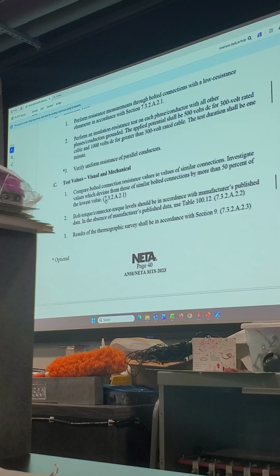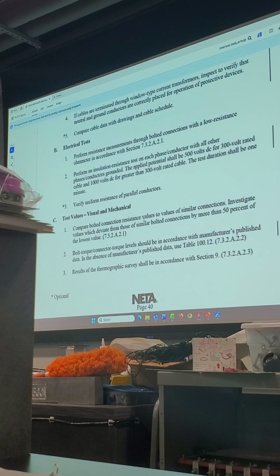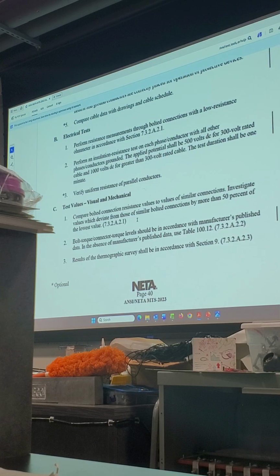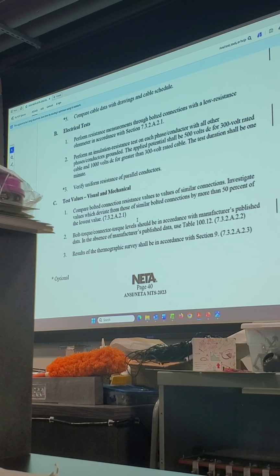So C, test values for visual mechanical: compare bolted connection resistance values to values for similar connections. Investigate values which deviate from those of similar bolted connections by more than 50% of the lowest value. That's what we'll be talking about today, along with our bolt torque and connector torque levels.